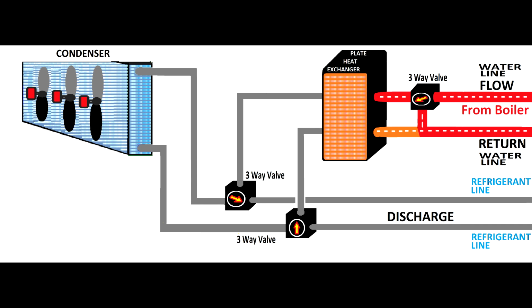However, a quantity of water will still pass through the plate heat exchanger. You can even see the color: it goes in red and comes out a little bit different, like orange, which shows it is not as hot. We just keep the plate heat exchanger warm, and you can also use electrical heaters for this plate heat exchanger if the temperature drops below zero. But in this case, you can see the three-way valve allows a quantity of hot water to pass through the plate heat exchanger to keep it above the freezing point, and the rest of the water is just diverted back into the heat exchangers inside the store.